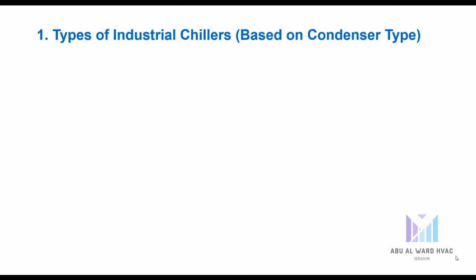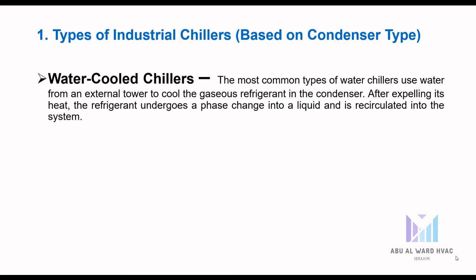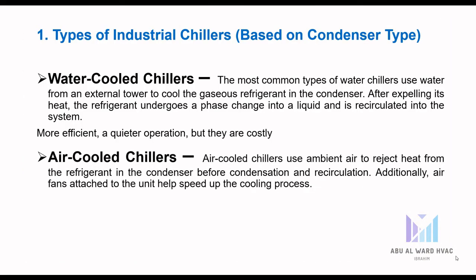Types of industrial chillers based on condenser type: water-cooled chillers are the most common type, using water from an external cooling tower to cool the gaseous refrigerant in the condenser. After expelling heat, the refrigerant undergoes a phase change to liquid and is recirculated. These are more efficient but more costly. Air-cooled chillers use ambient air to reject heat from the refrigerant in the condenser, with fans to speed up cooling. They are cheaper than water-cooled but noisier.